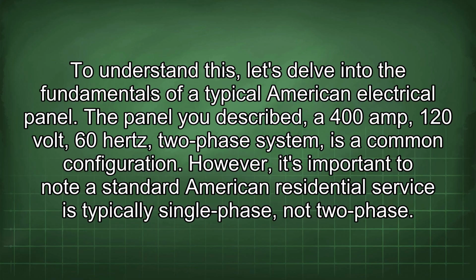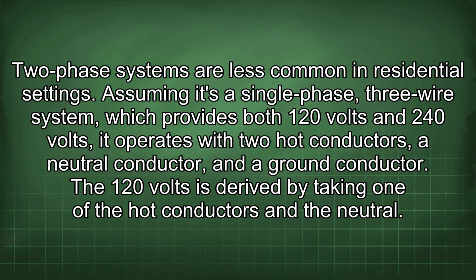The panel you described, a 400 amp, 120 volt, 60 Hz two-phase system, is a common configuration. However, it's important to note a standard American residential service is typically single-phase, not two-phase. Two-phase systems are less common in residential settings. Assuming it's a single-phase, three-wire system, which provides both 120 volts and 240 volts, it operates with two hot conductors, a neutral conductor, and a ground conductor.